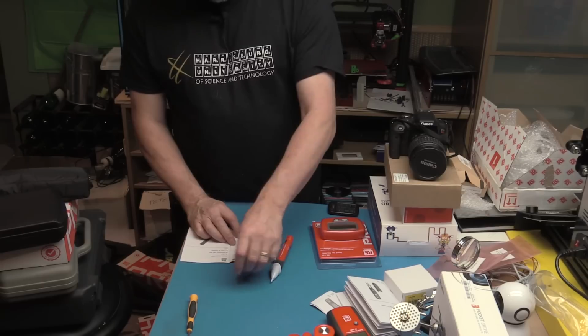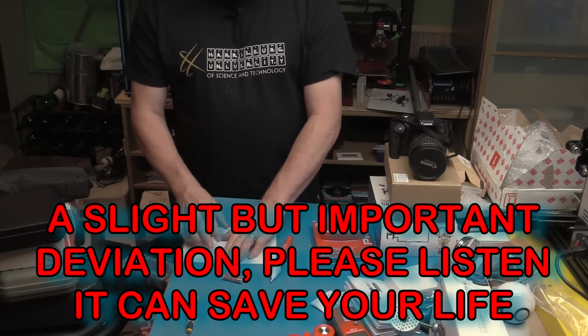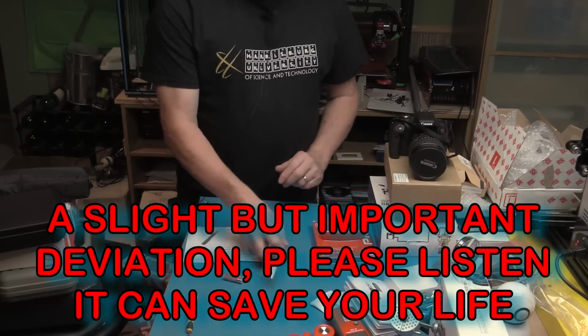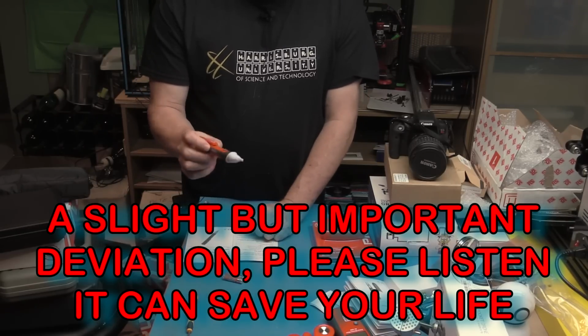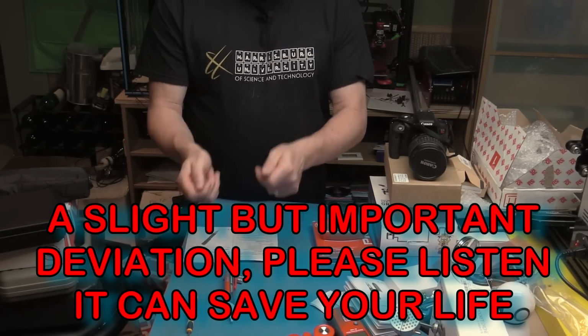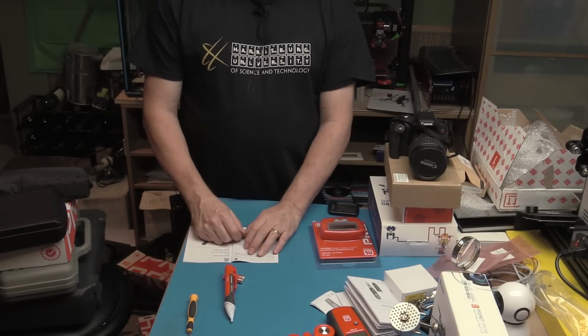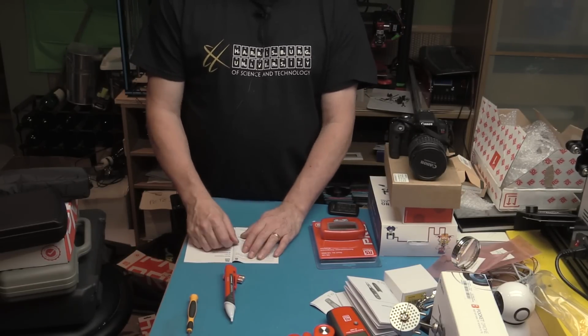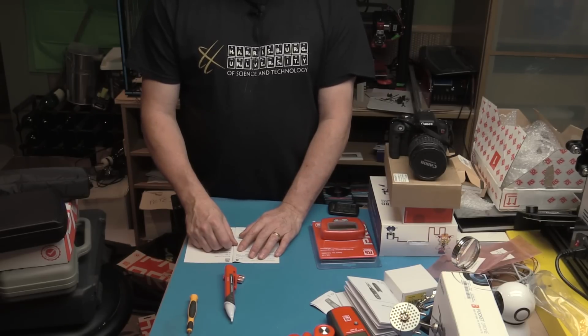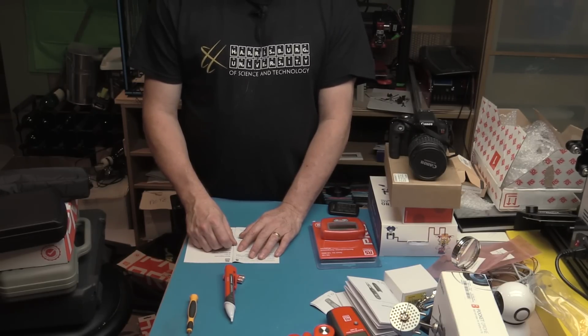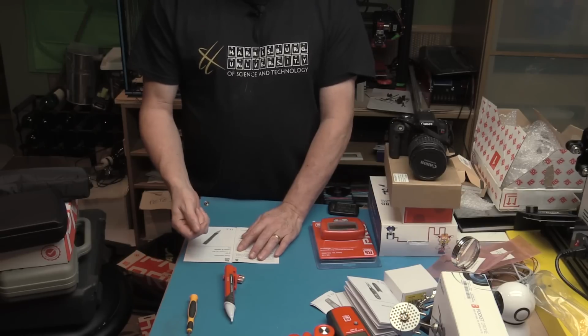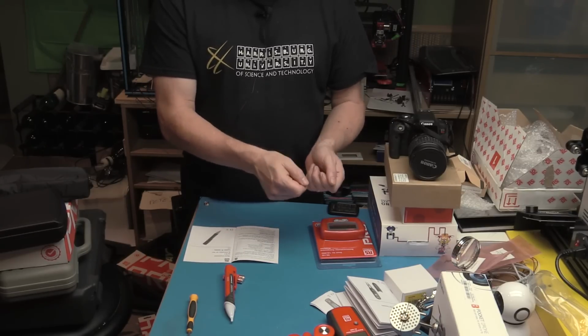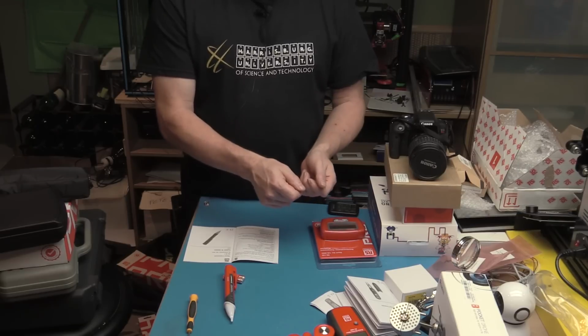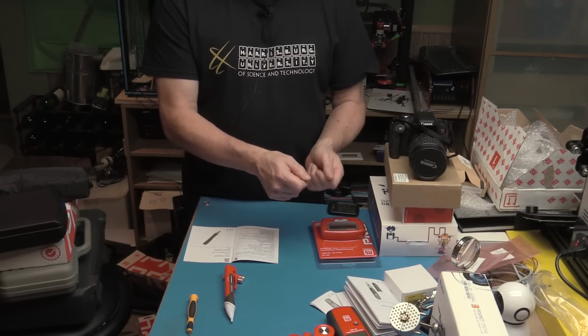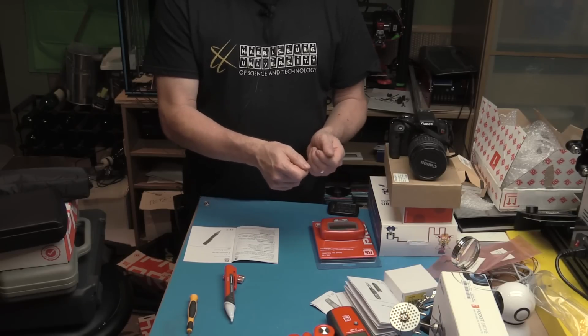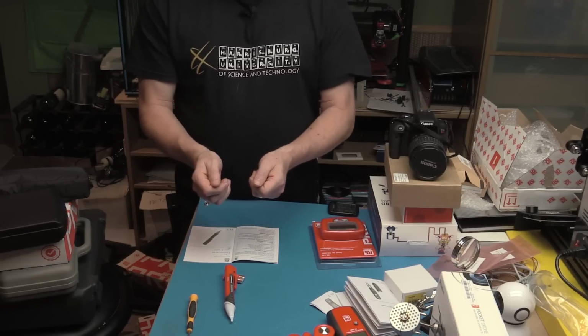This is something that is not, I think, emphasized enough in testing. When you're testing something, people will take a multimeter and stick it across a pair of contacts and say, oh, there's no volts there, and then they'll go away and they'll put their stuff on and they'll start working and then suddenly electrocute themselves. And the reason for that is because they haven't verified that the multimeter, for instance, is working properly. So put it onto something that is going to make a measurement that you know will give you a reading. When you know that that is giving you a correct reading and what you expect, either by continuity or voltage AC reading or whatever it is you're supposed to be reading, then go do your measurement.